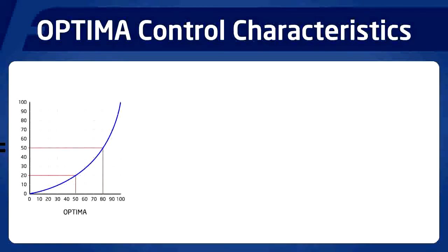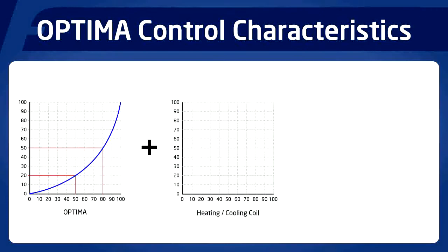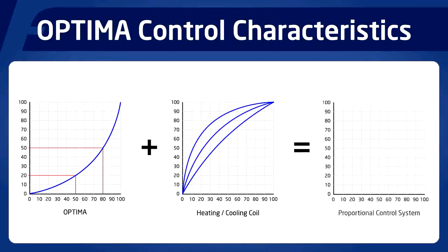When this equal percentage control valve, which is always this shape due to the authority of 1, is combined with the equal percentage but opposite characteristic of the output from the cooling or heating coil, then irrespective of the exact shape, which is affected by delta T and whether you're on heating or cooling service, these two characteristics combine to provide the proportional relationship for the control system as a whole.